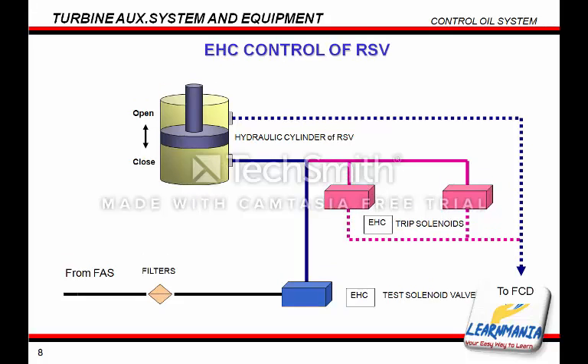This figure shows an outline of the control system for the RSV hydraulic cylinders. Note that a test solenoid valve is attached instead of a servo valve. The purpose of this valve is to test the RSV function during normal operation. While the solenoid valve is energized, the RSV will be closed and will fully open when the solenoid valve is de-energized.